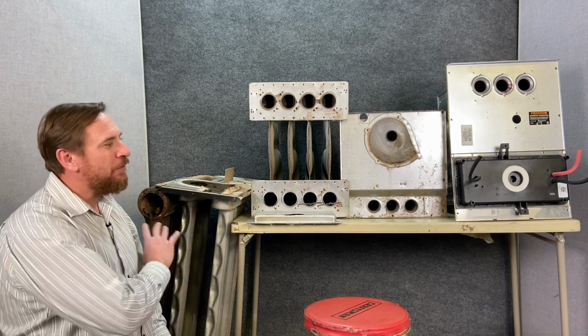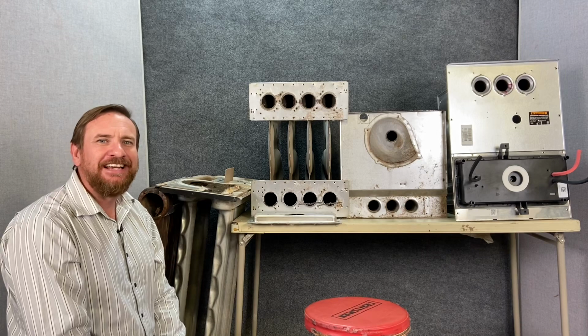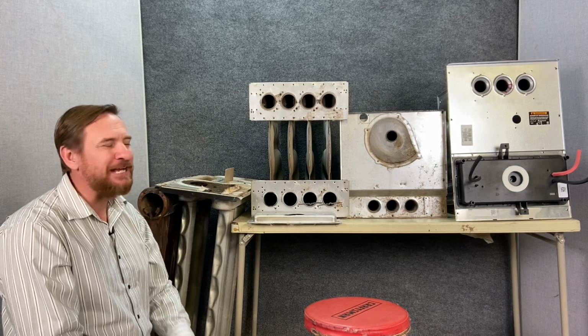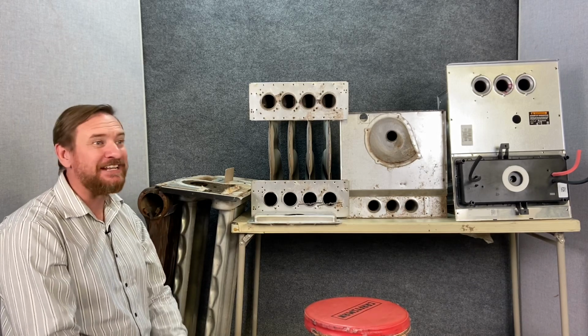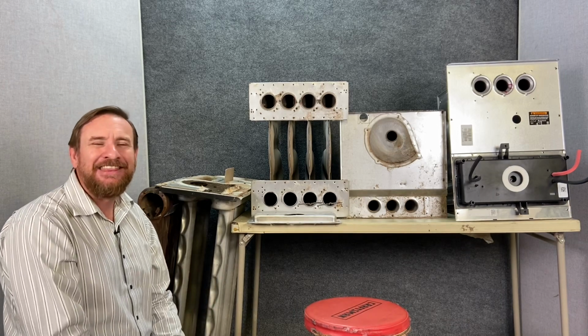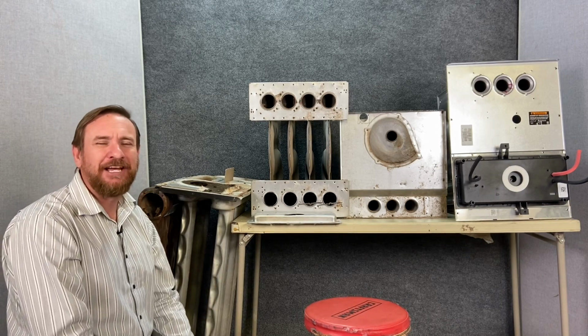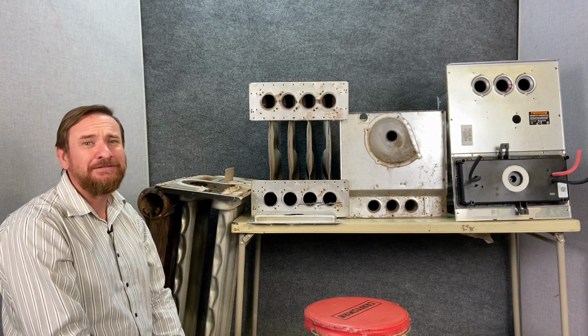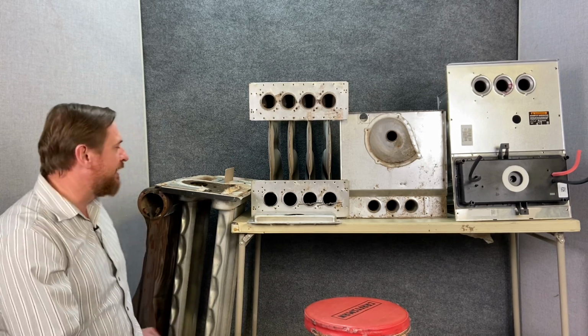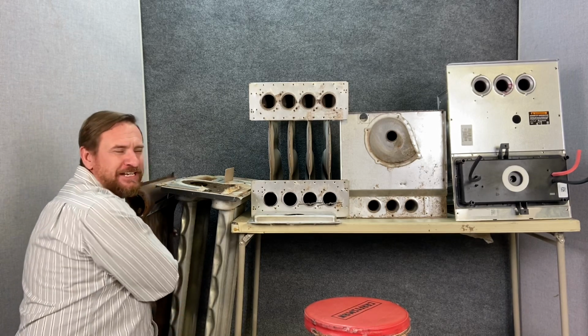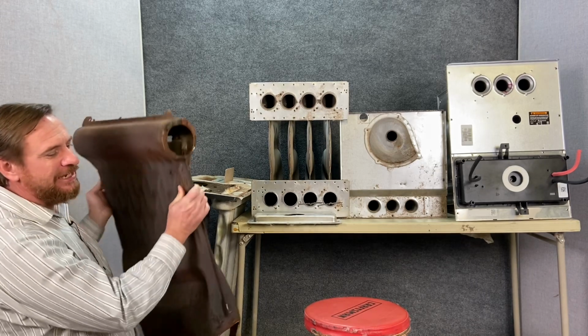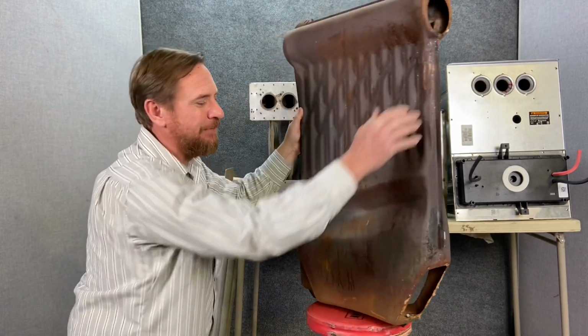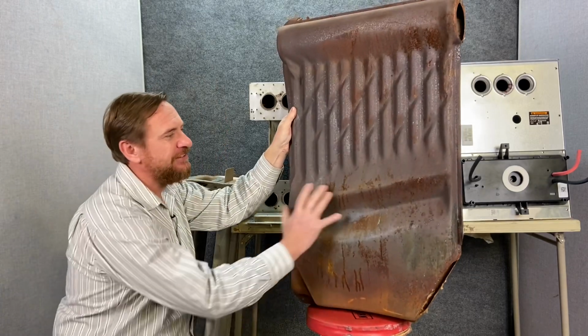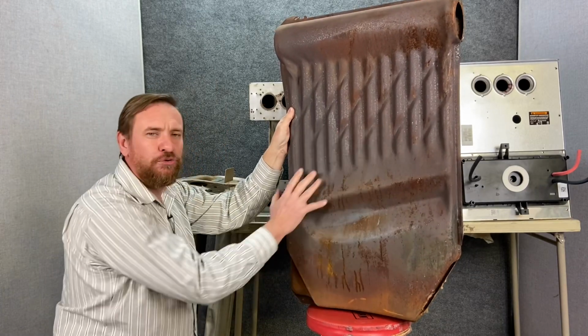the houses. One of the heat exchangers that I do not have here is a cast iron heat exchanger, and I am so glad that I do not have one of those, and I hope I never see one again. They were so horribly heavy, having to take them out of basements, out of closets, and sometimes even out of attics. They were an absolute nightmare. But after the cast iron heat exchanger came these, and these were more workable because they were a type of stamped steel.